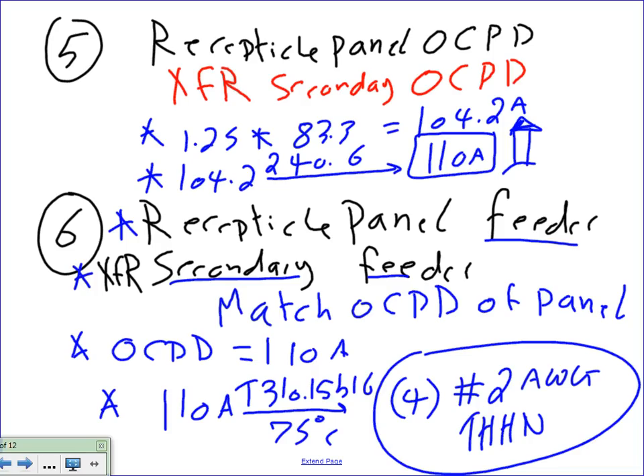Number 2. Any question? Why didn't we go to Table 450.3(B) for step number 5? You can. If you go there, what's your multiplier for step number 5? 1.25. So, almost the same, so it's a wash. It's a wash. If you want, that's where this will act as a continuous load for the circuit breaker as well. So if you want to, what's the table, 450.3(B) or 8? 3(B), yeah. You're absolutely right. It's the same.